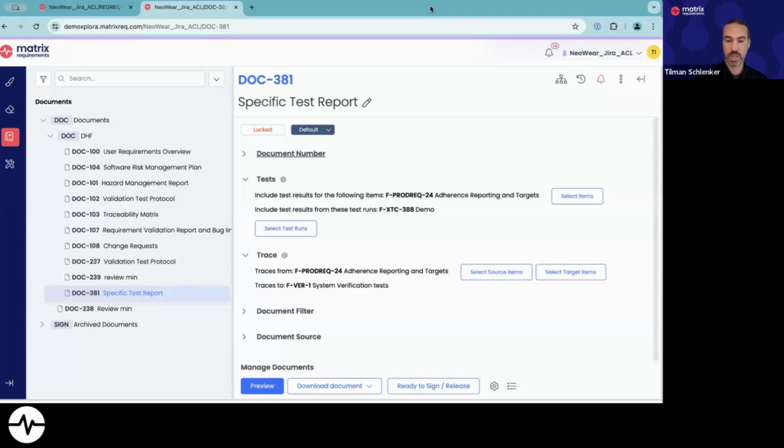That has to be available somewhere, but you don't need to document it for your final submission. So there needs to be a different pipeline, effectively, where you pull in the same results for the final release, just to document that you have been doing all of these tests on it. And this documentation has to be complete. So one of the things you can do is, for example, create a verification item in Matrix that is basically a placeholder with the documentation for what some kind of automated test is doing.